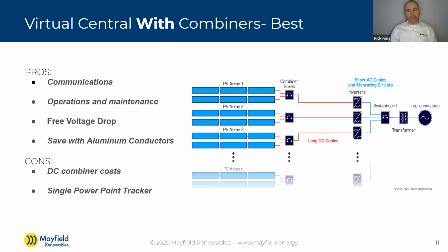And if you're going to start going to a 2000 volt DC system, your first challenge is going to be, what's the AC output of that? You already see that at the 1500 volt, most of the inverters are outputting 600 volt, not 480. So you need to get 600 volt AC panel boards, switchboards, etc. If you go to 2000, you're probably not even going to stick at that 600. You're going to have to go to 1000 volt AC. Now you're in medium voltage kind of land.